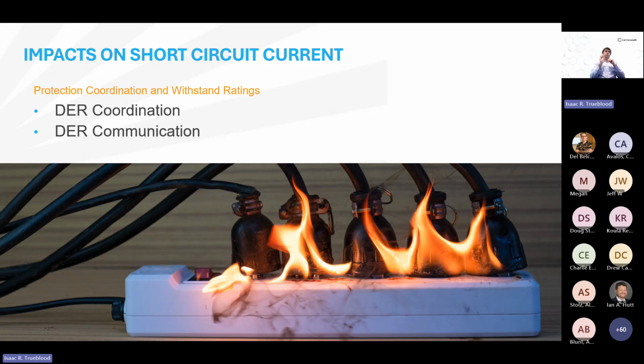This can especially be true with inverter-based resources, as they provide much lower short-circuit current than synchronous generation. However, tighter does not mean impossible, and with proper protective equipment and protective settings, distributed energy resources can be safely added to the distribution systems. This will still require an examination and possible upgrades or setting changes to existing feeder protection or protective equipment to ensure proper coordination and ratings.